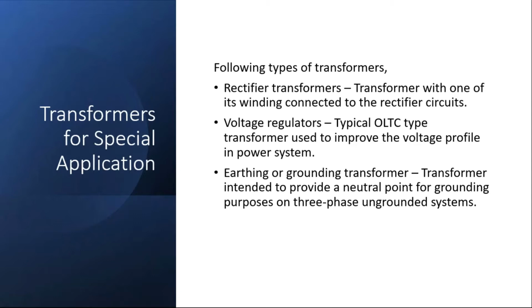And the third one, more from the system configuration and protection point of view, is earthing or grounding transformers. These are used where the system does not have a grounding point, and the customer needs the transformer to provide a ground point to limit the fault current.